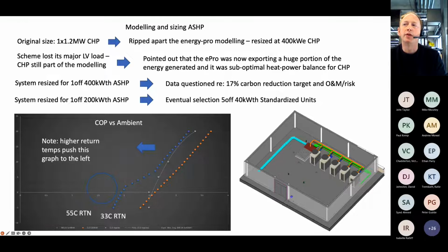The actual output was pretty appropriately sized for an air source one-fifth its size, and it was better, but not by much. And the linear aspect of the orange line was the real giveaway. And you throw in the real world stuff, the ease of maintenance, the ease of replacement, the standardization and ubiquitousness, if that's a word, of these types of small units versus the fairly bespoke and kind of risky nature of going for one large unit. And we concluded that a sensible operator would go for smaller units.